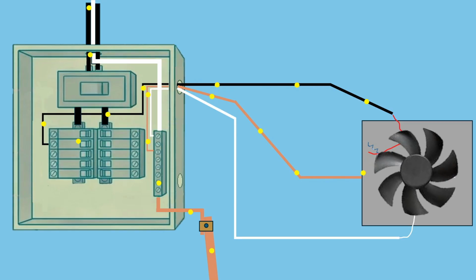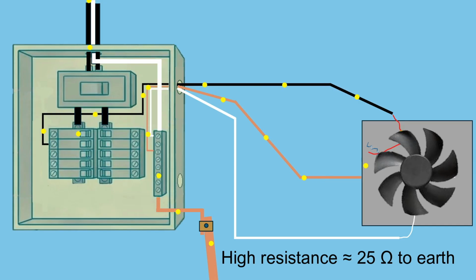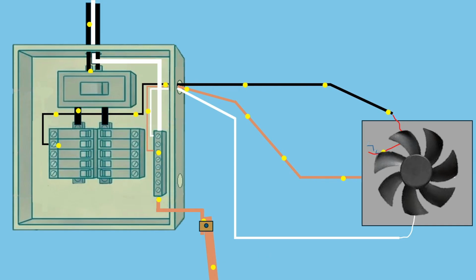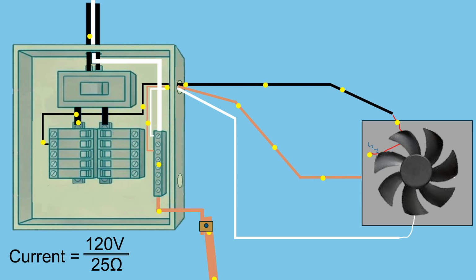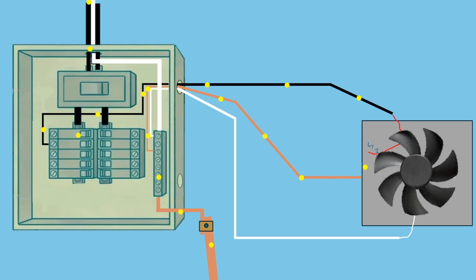Let's put some real numbers to this. A typical grounding electrode system has a resistance to earth of around 25 ohms or more. That resistance comes from the earth itself, not the metal rod. If you applied 120 volts across that resistance, Ohm's law tells us that the current would only be a few amps, often about 5 amps or less. That's nowhere near enough current to trip a 15 or 20 amp circuit breaker.